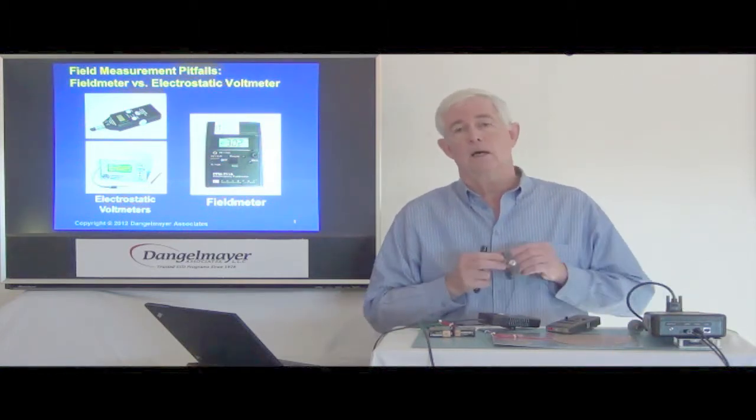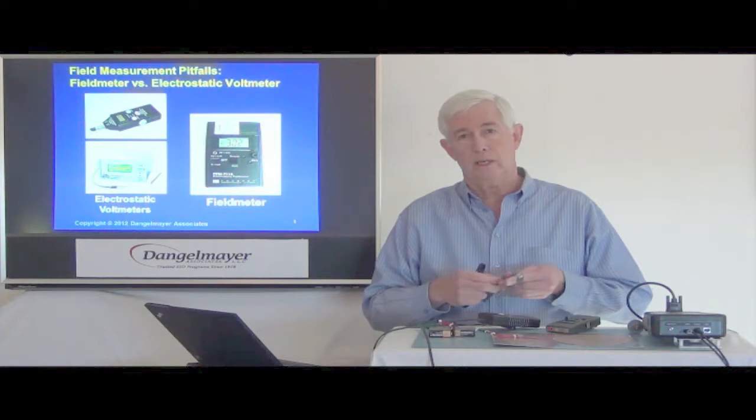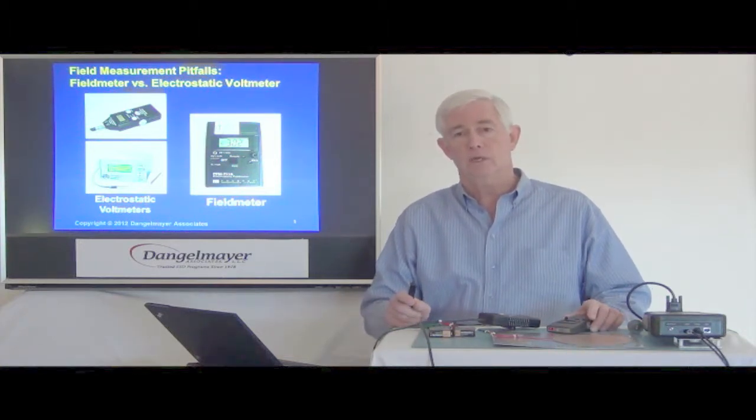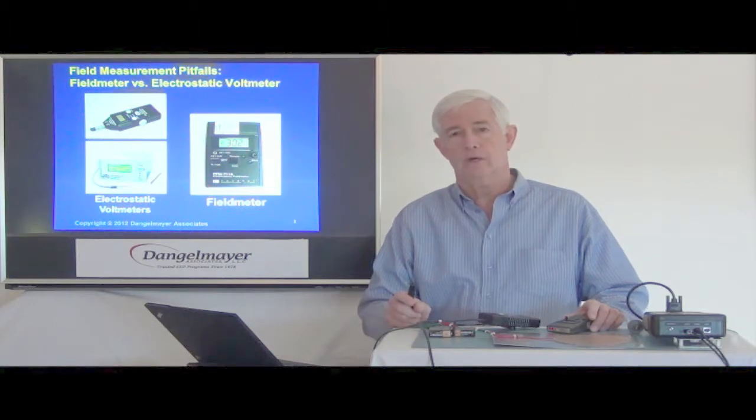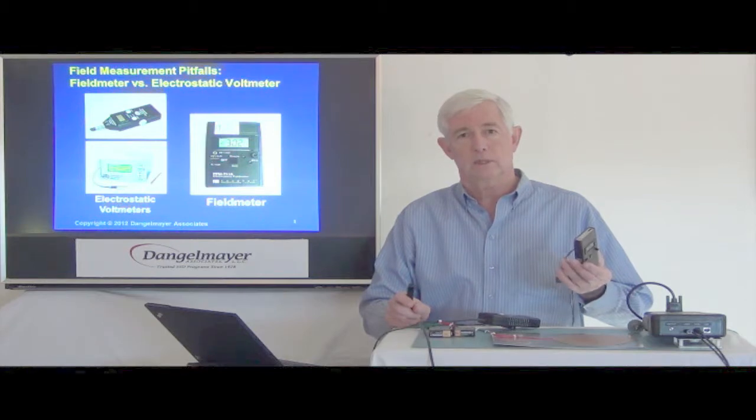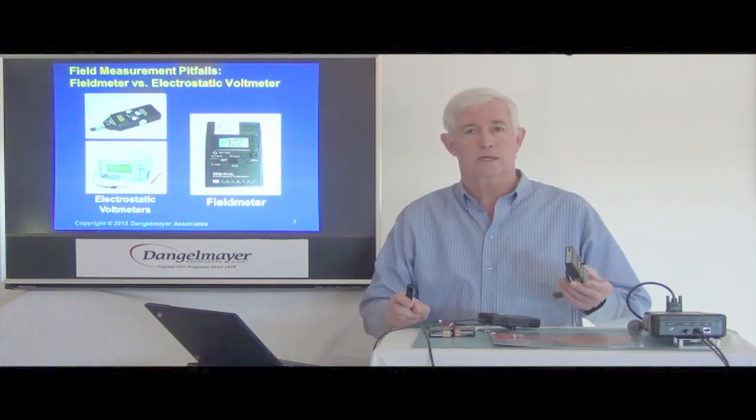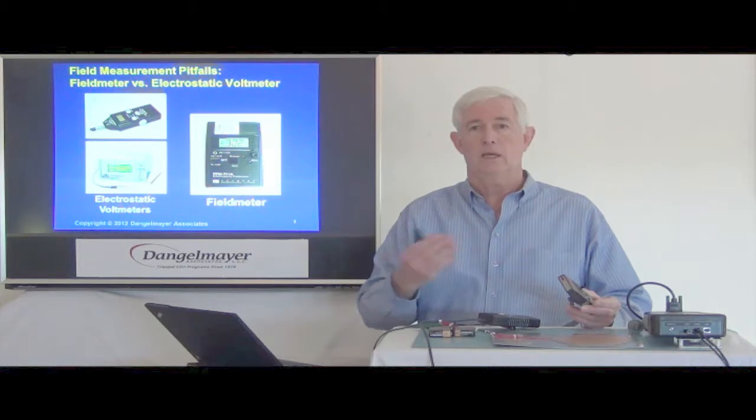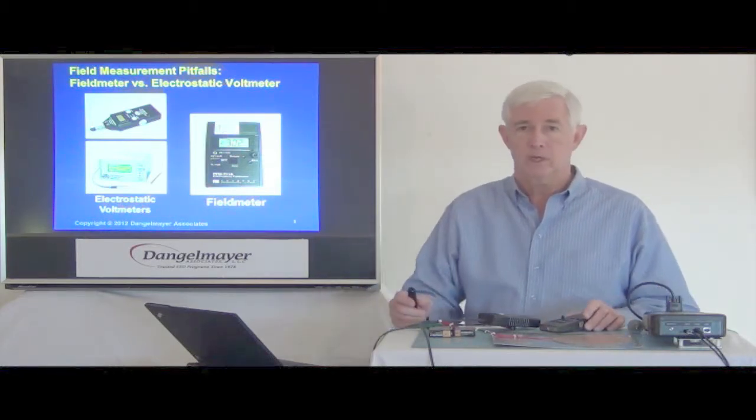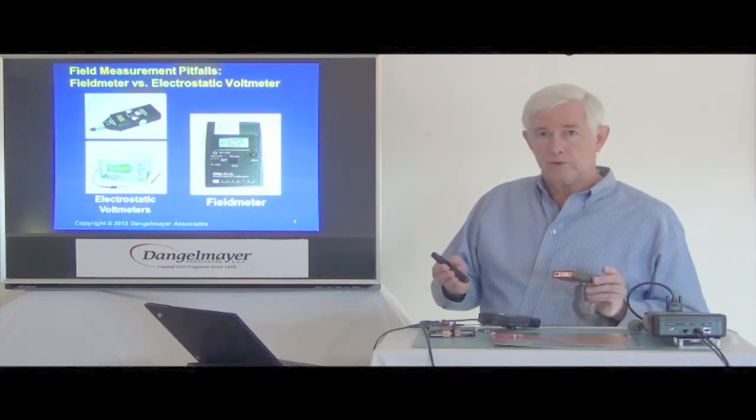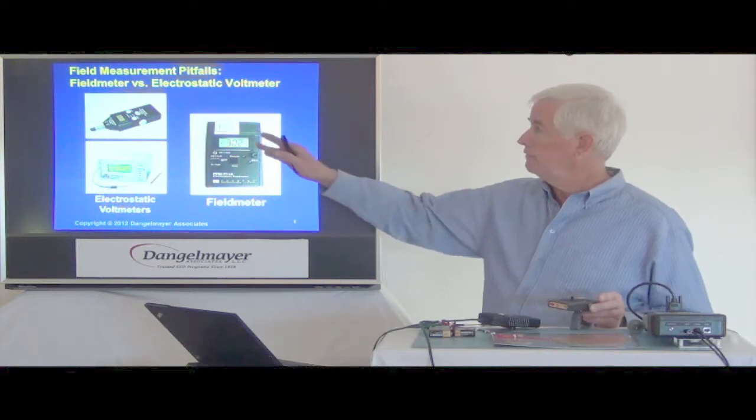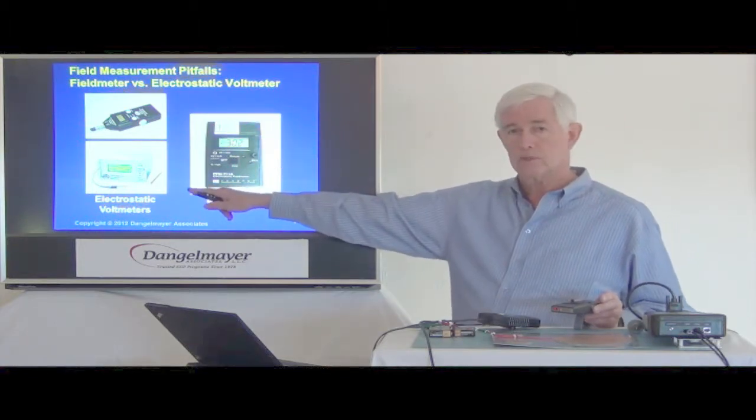In fact, I'm going to put my wrist strap on now and tell you that we were sent all the way to Korea because the engineer of one of our customers did not know how to use the meter. He was reporting unusual voltages, and it turns out that he was not grounded, and the meter was giving us a false reading because of that. So you and the meter both need to be grounded, very important, and that's true for the electrostatic voltmeters that we'll be discussing as well.